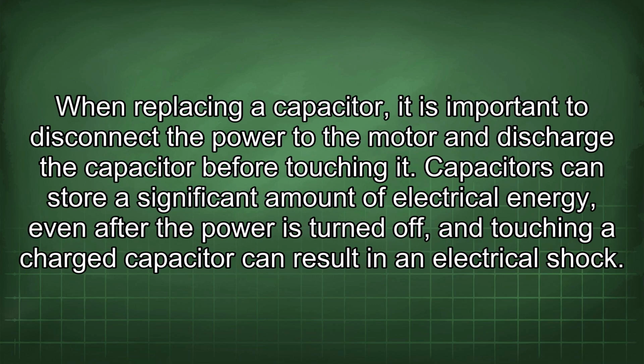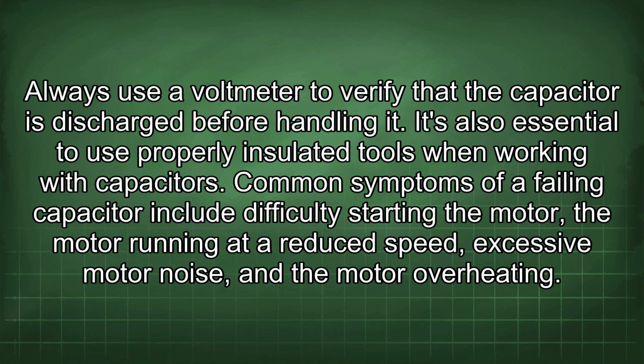When replacing a capacitor, it is important to disconnect the power to the motor and discharge the capacitor before touching it. Capacitors can store a significant amount of electrical energy, even after the power is turned off, and touching a charged capacitor can result in an electrical shock. Always use a voltmeter to verify that the capacitor is discharged before handling it. It's also essential to use properly insulated tools when working with capacitors.